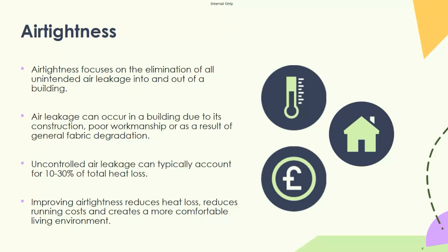And so, if you've ventilated cavities, for instance, air leakage being able to go up the cavity, through plug sockets, through service penetrations, up the cavity, out the wall plate at the top, it's completely negated external wall insulation that you might have applied potentially. So it's a really important proportion of your overall heat loss. You may well apply insulation, reduce that thermal transfer through the fabric itself, but if air can move around and bypass it, then that's not what we want.